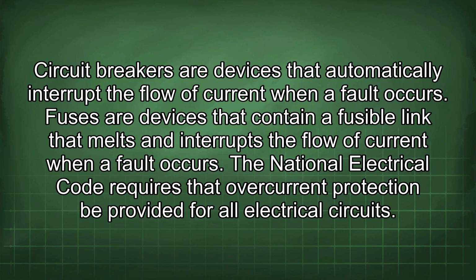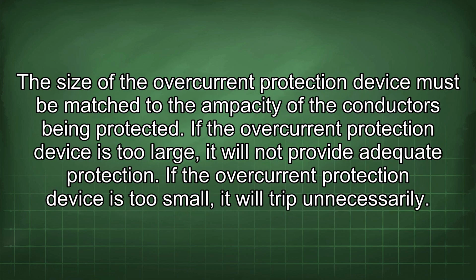The National Electrical Code requires that overcurrent protection be provided for all electrical circuits. The size of the overcurrent protection device must be matched to the ampacity of the conductors being protected. If the overcurrent protection device is too large, it will not provide adequate protection. If it is too small, it will trip unnecessarily.